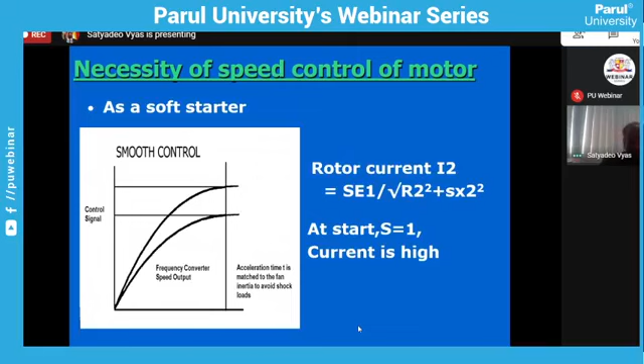You can see if I start the motor on DOL, it takes about 600% current. In case of a star delta starter or soft starter, even 250%, even 200%. So drastically, inrush starting current can be reduced by the use of a starter.